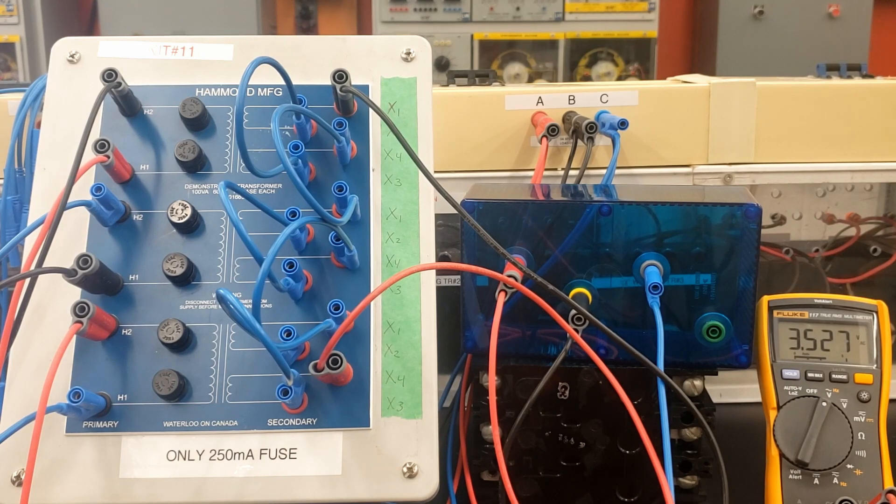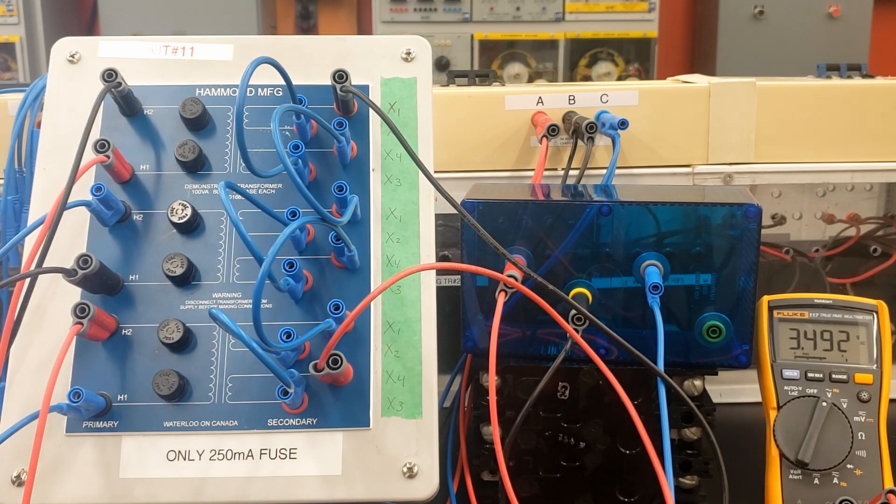Hopefully everything made sense to you. This was the closed delta where we had 208 volts three-phase in and 240 volts three-phase out — because we seriesed up the X2 and X3 connections. If something's not clear, leave some comments below for this video. The next one is going to be a delta to Y connection, so check out the next video in this playlist.